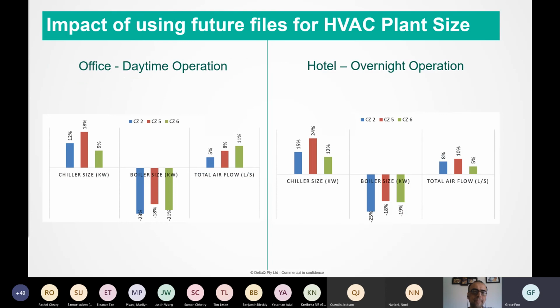So what we then did was, using the Camel software, try to determine what the actual chiller, boiler, and air handling plant requirements were. And we did that for 2 sets of buildings, one representing daytime only operations, so that's our standard office building, and then one representing a building that operates 24/7, so that's where your overnight temperatures actually impact operation at the hotel.